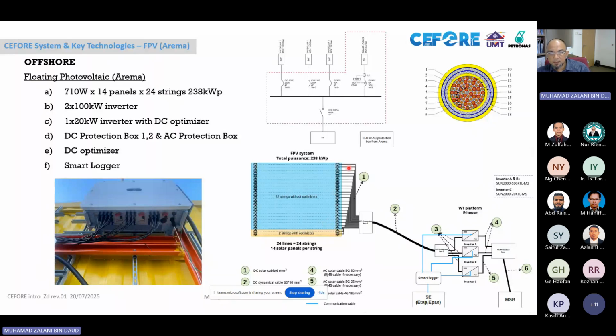So from this panel, the DC power is transferred through the dynamic cable, the DC dynamic cable. We have a DC protection box here at the floater and also at our platform. Then we have 3 inverters feeding the same bus bar, which is the 400 volt bus bar, and then the rest of the power will go to the MSB inside the e-house.